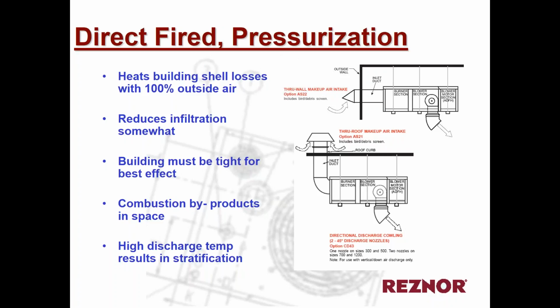The other problem or issue is that the combustion byproducts are entering into the space. So you have to make sure that you have proper ventilation so that we don't get condensation of the water vapor and the flue gases in the space. But we do offer these, and if you have a customer that is looking for a Cambridge type unit, we can certainly offer it to them.